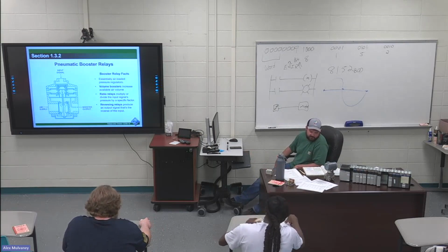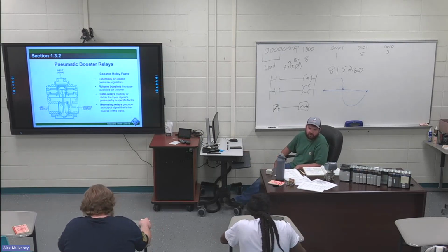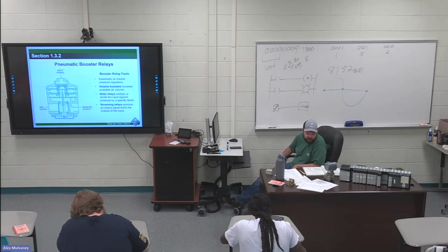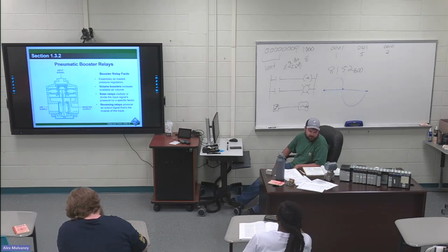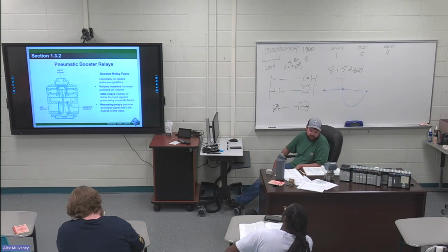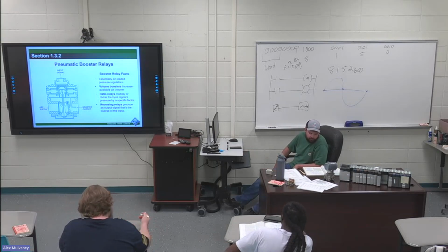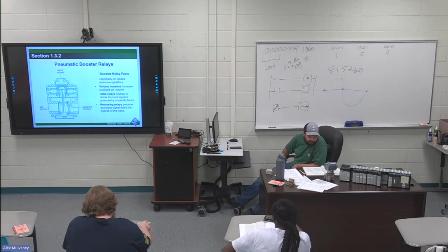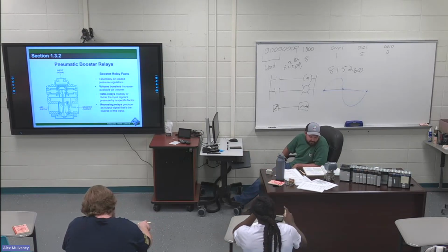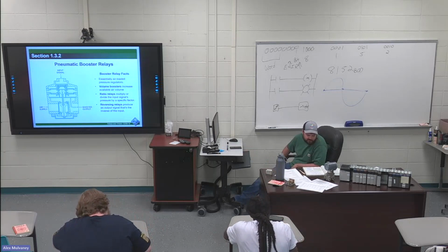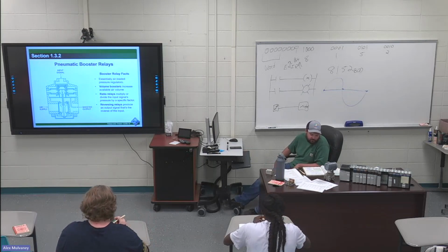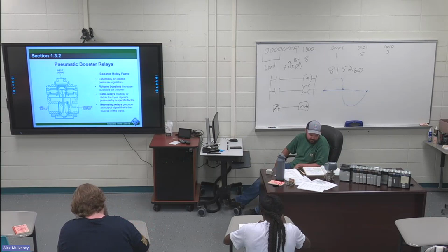Page 11, booster relays. First sentence of 132 is an online test question. Booster relays are essentially air-loaded, self-contained pressure regulators. They're classified into three broad groups, and I've got the second two highlighted. You're gonna have a few questions come out of the second two bullet points. Ratio relays used to multiply or divide the pressure of an input signal. And then the last one, reversing relays that produce a decreasing output signal for an increasing input signal.